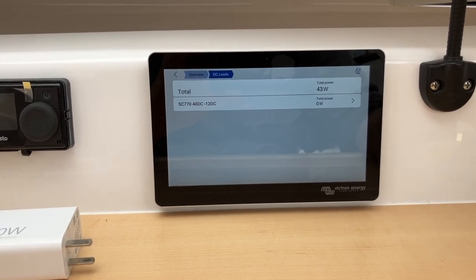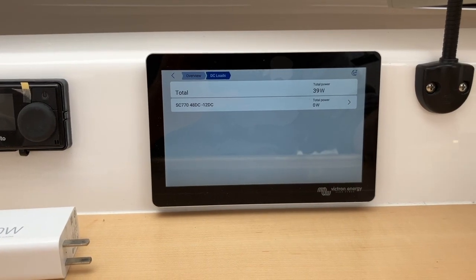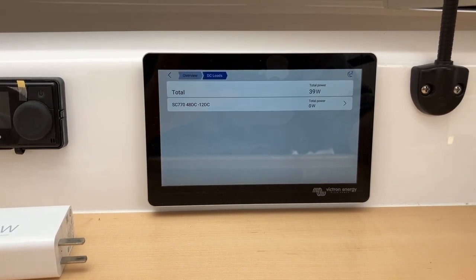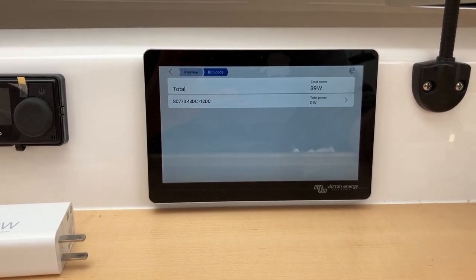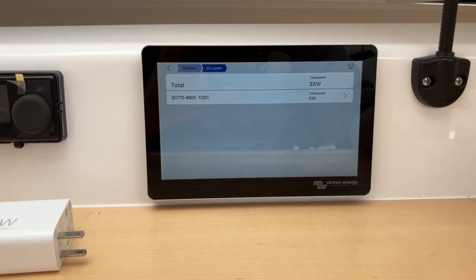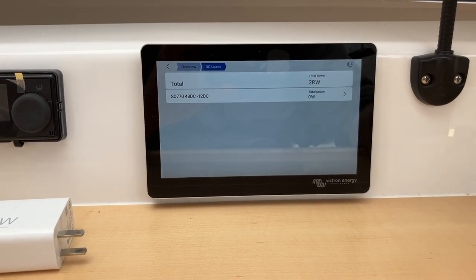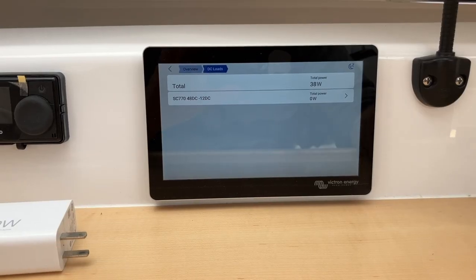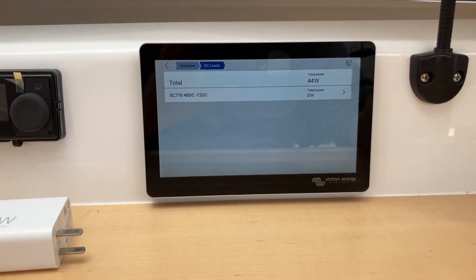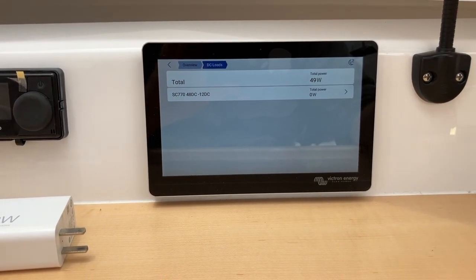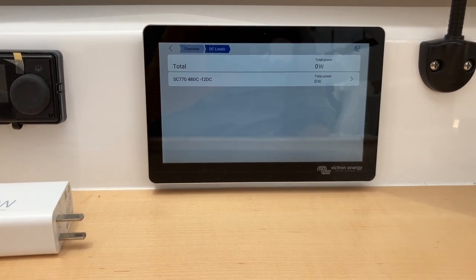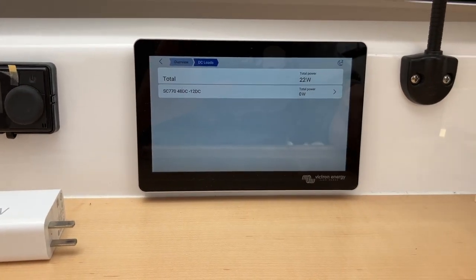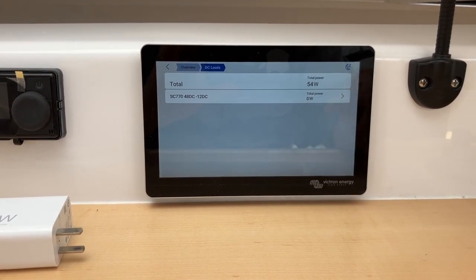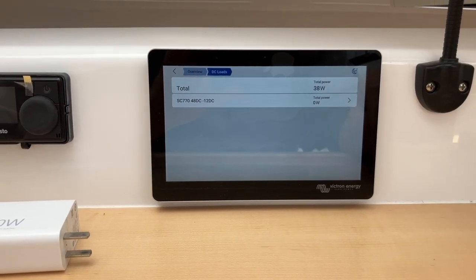Then we check — is the solar keeping up? If it is, great, the converter doesn't come on. If the solar doesn't keep up and the battery goes back down to 50%, that's our backstop, and we turn the DC-to-DC on again to charge the battery back to 100%, then see if the solar can do it again. This boat has gone with the option of solar blankets on the front tramp, so when you're anchored, you put the solar blankets out, which helps keep the house bank up, and you may not need to draw off the 48. Okay, we'll go back again.